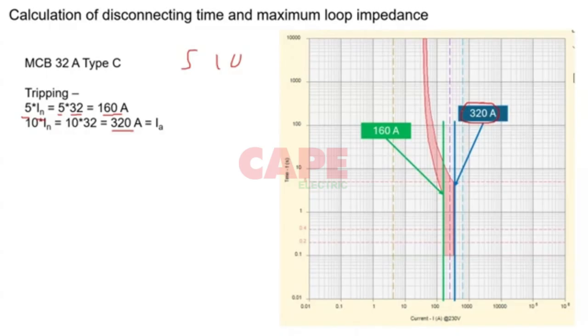So if you look at this characteristic, within 0.1 seconds it is going to trip at 320 amps or at 160 amps. But if the current falls a little short, probably somewhere around this region, then it is going to take close to 6 to 7 seconds to trip. This is what it means. So you are supposed to limit it to 160 to 320 amps. So we are going to take 320 amps here for the calculation.